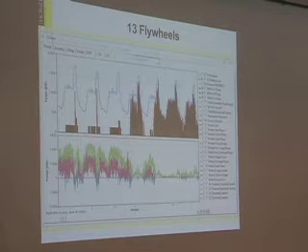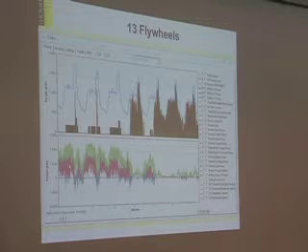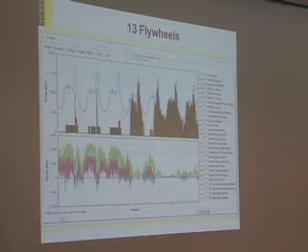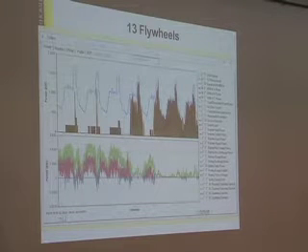So we have all this excess, or secondary load, or whatever, excess energy, and some of it's coming from the wind. It's impossible to distinguish where the electrons are coming from. Is the power going to the secondary load diesel power or renewable power? Is it because the wind's blowing too strong, or is it because our minimum load constraint is too high? Electrons are electrons.